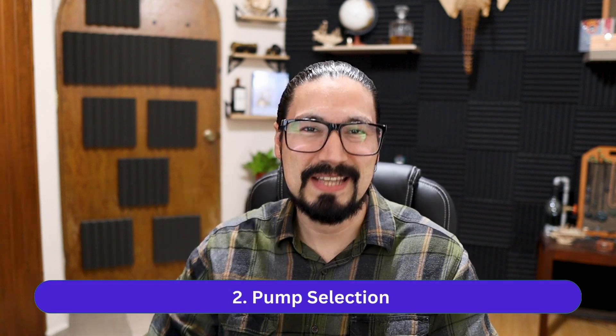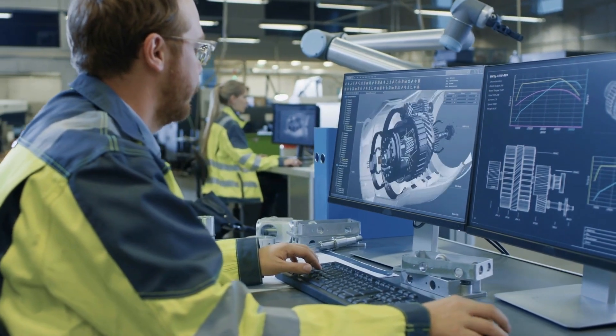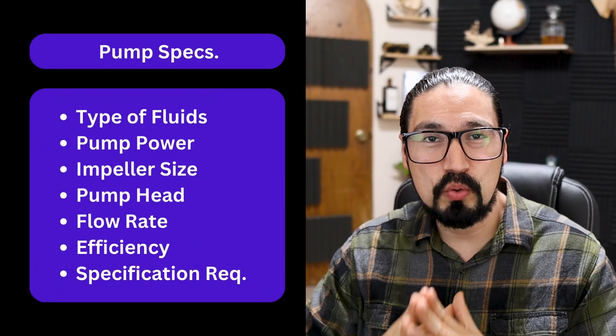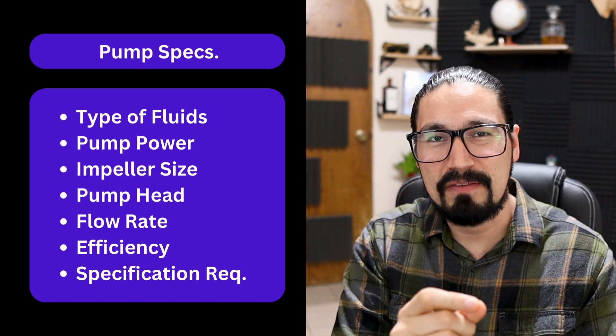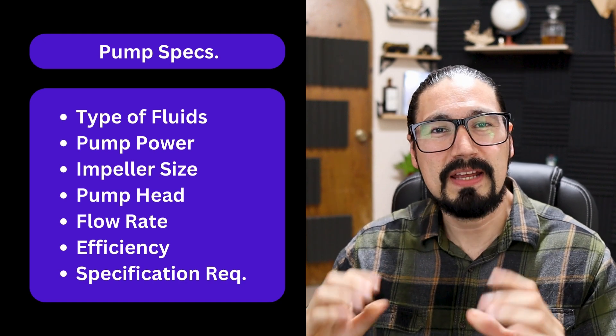The very first steps involve pump selection. If you have incorrect pumps — pumps that are oversized or not suited to the required temperatures, pressures, or viscosities — you need to select the correct pump. This requires knowing your system properly and the types of pumps available, including fluid types, impeller size, head, flow rate, and efficiency specifications.